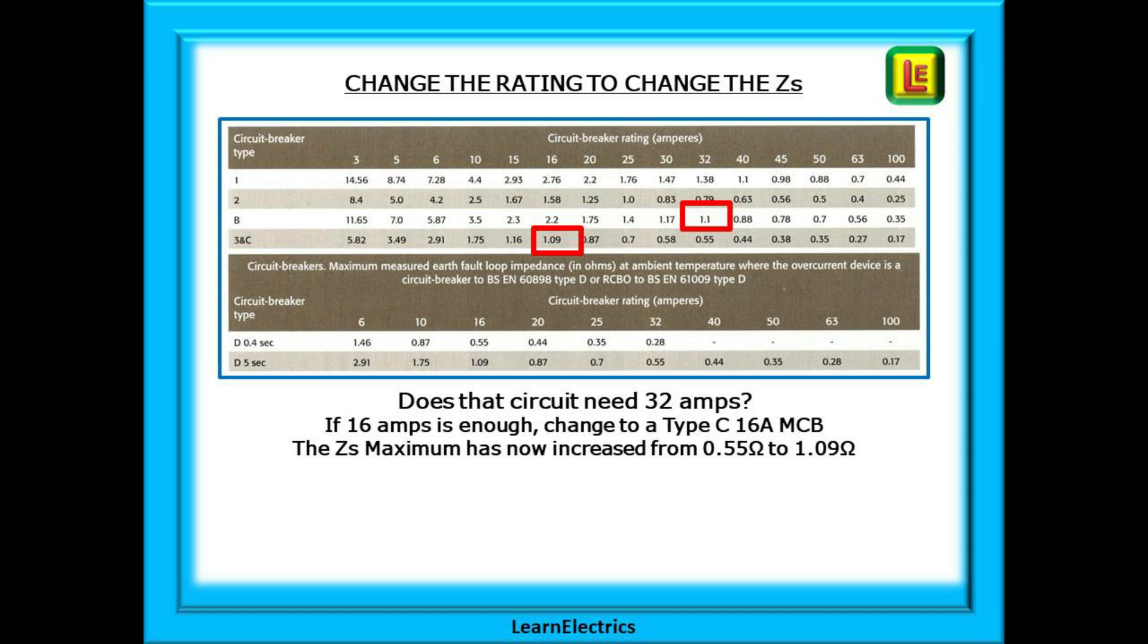Look at the charts shown. A C16 MCB has a maximum ZS of 1.09 ohms and our actual ZS of 1.07 ohms is lower than this and is an acceptable reading. So we cannot move the machinery to make the circuit shorter and we cannot rewire in larger cable. Our solution then is to change the original B32 MCB for a C16 MCB and all is well again.